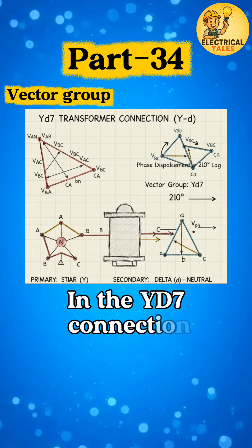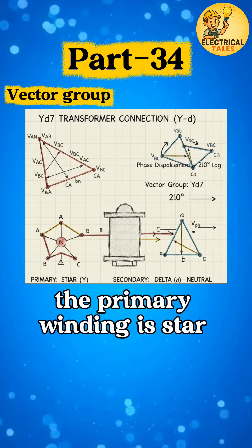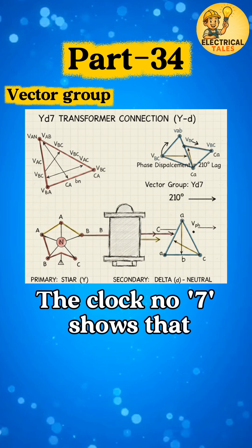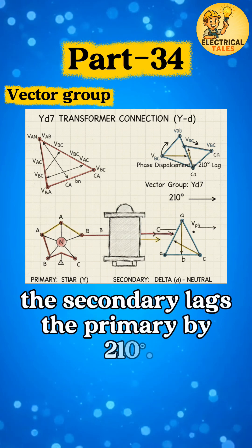In the YD7 connection, the primary winding is star and the secondary is delta. The clock number 7 shows that the secondary lags the primary by 210 degrees.